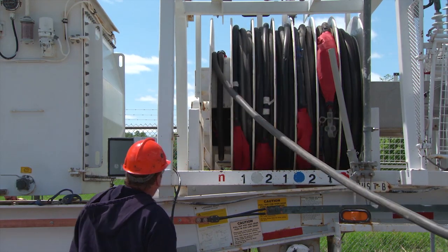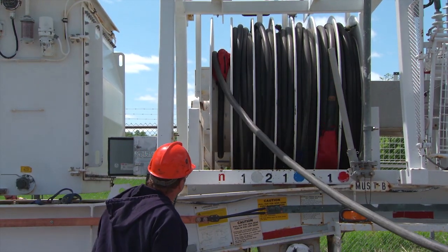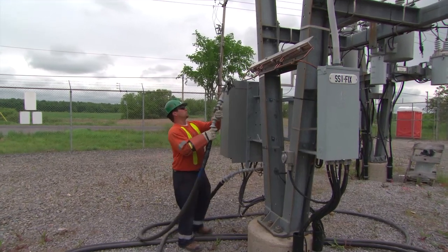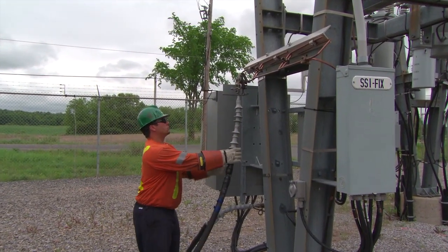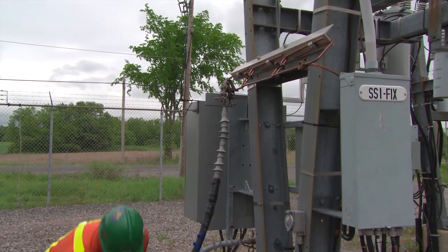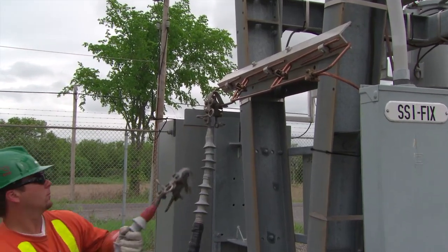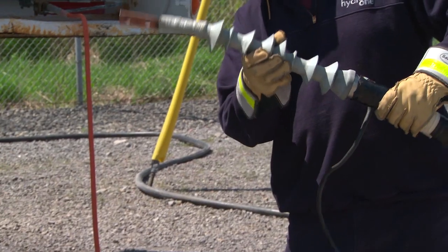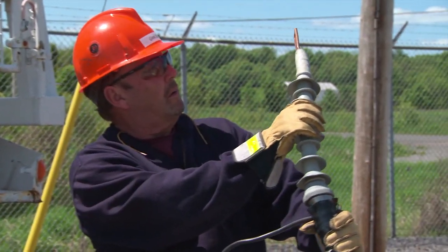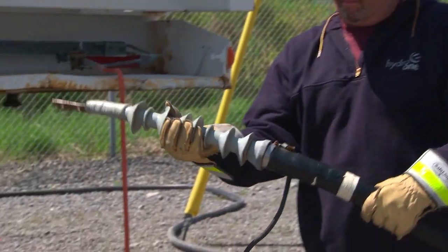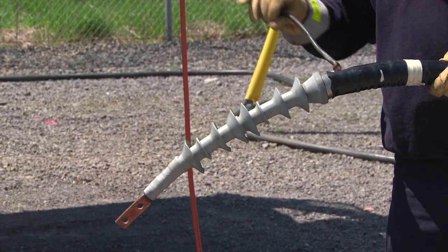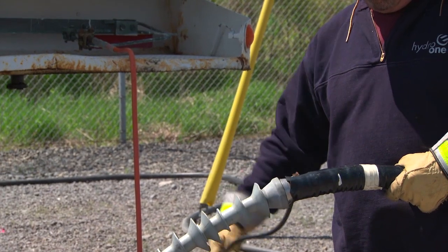Once the cable has been removed from the reel, remove the protective cover on the load end and place the end on a portable ground stirrup or station ground stirrup. Check the high pot test date. This date will either be marked directly on the cable or be included in the annual inspection report.